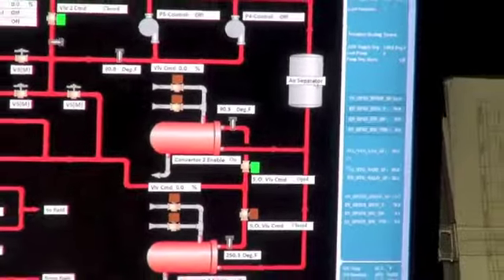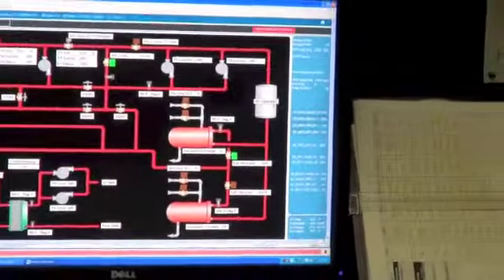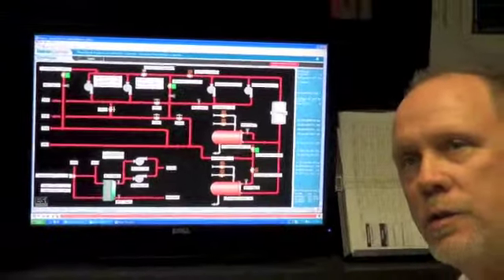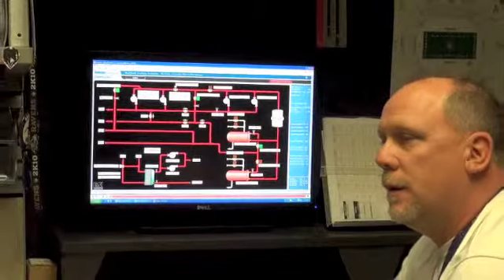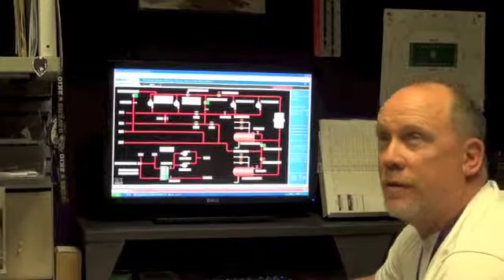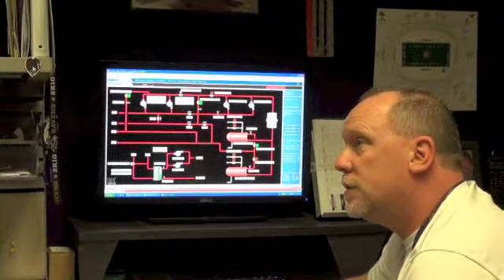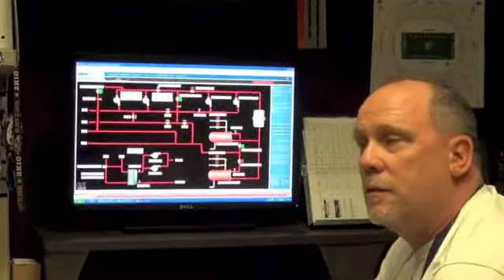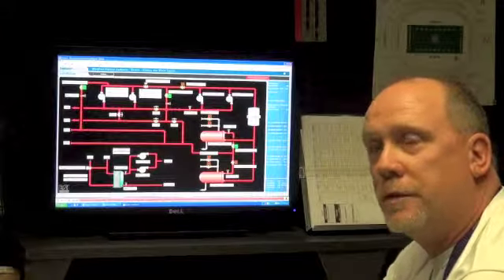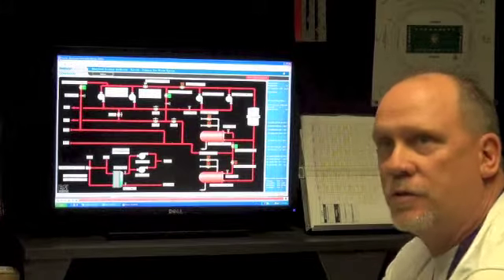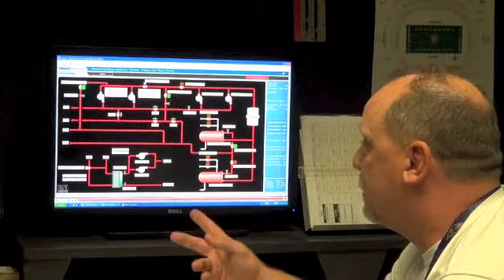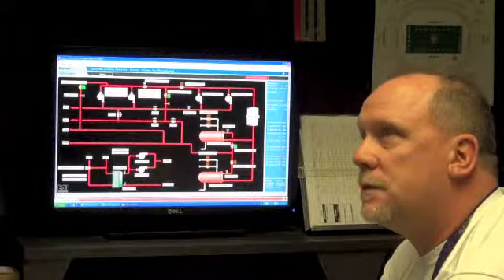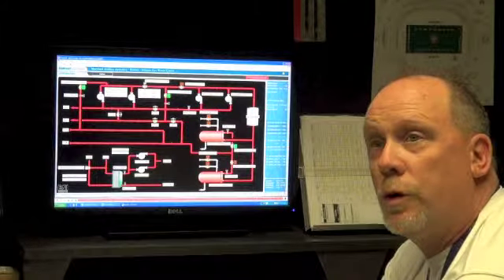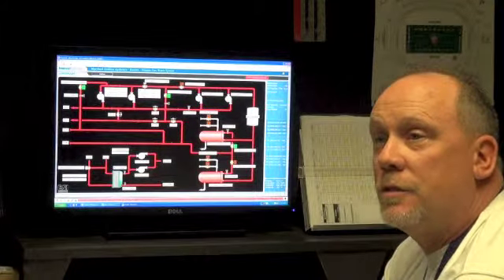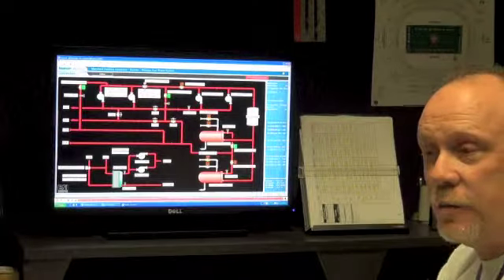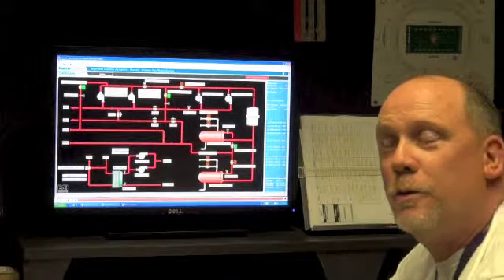That's a work in progress right now because we're in the process of changing over the control system for that system. We also have a leak in one of the zones. We have 6 zones out on the field. One of them has a leak right now, so we're trying to get that leak fixed before the season starts. But we can probably heat the field up to about 70 degrees on a cold day, which is why you see a lot of fields where you see the steam coming off the field when it's real cold. That's why.